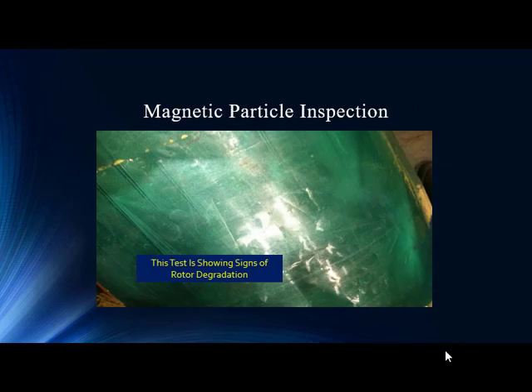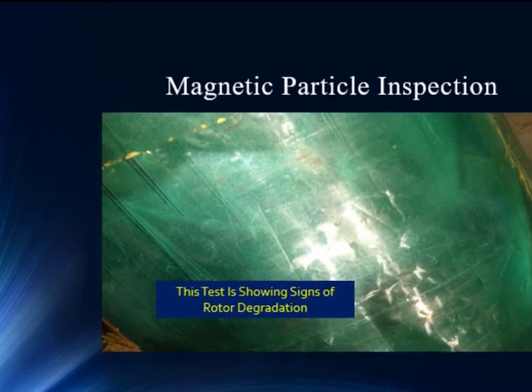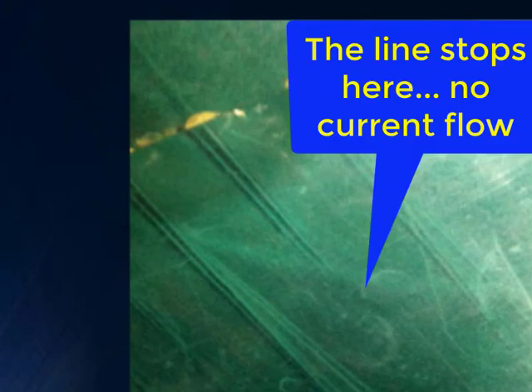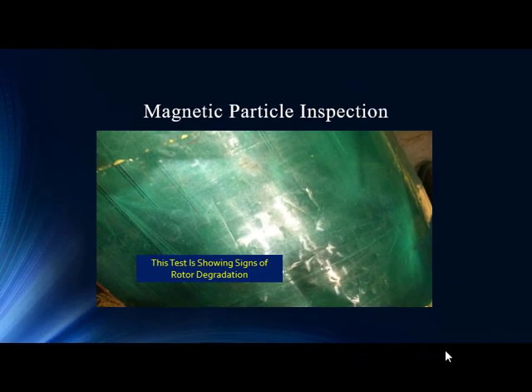The next test is a magnetic particle inspection. They separate the rotor from the stator and put a magnetic coil on the rotor, which induces current flow into the rotor bars. The magnetic particle paper contains small pieces of magnetics that float around and naturally collect around the rotor bars if they're conducting current. In this case, there are not a lot of dark bars running through that paper, showing that the expected current flow through the rotor bars is simply not occurring.